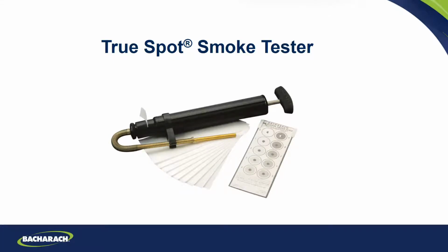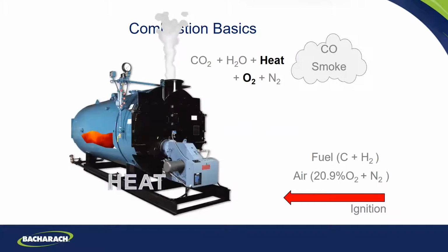You want to go by your burner manufacturer specifications. Almost all of them are trace smoke and/or no smoke. And if it's not there, if it's a higher number, you want to work on it so that it is lower, and then you're not going to soot up your oil burner, or you're not going to send that soot through your instrument. Okay, getting back to these gases.